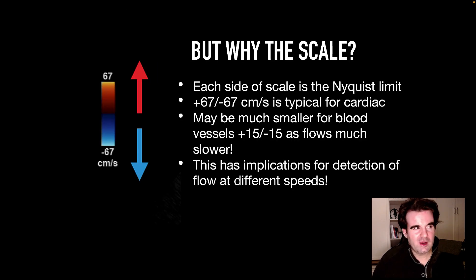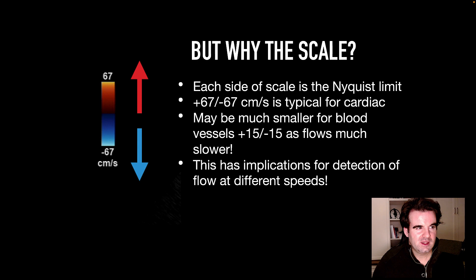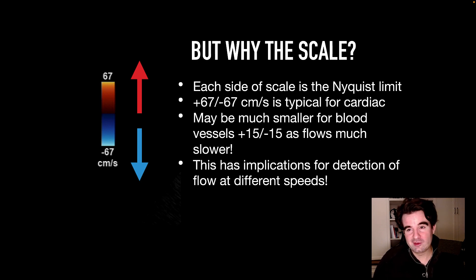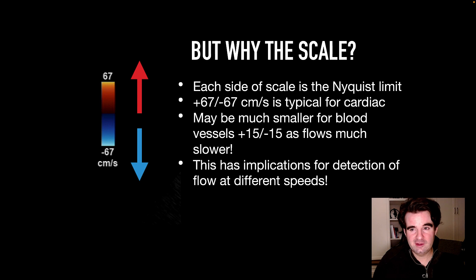You may be wondering why there is this scale. Each side of the scale is called the Nyquist limit. Here we're seeing plus or minus 67 centimeters per second of actual blood flow, which is typical for cardiac imaging — somewhere between 60 to 70 centimeters per second. It would be much smaller for blood vessels, around plus or minus 15, as flows can be much slower. This has implications for detection of flow at different speeds.